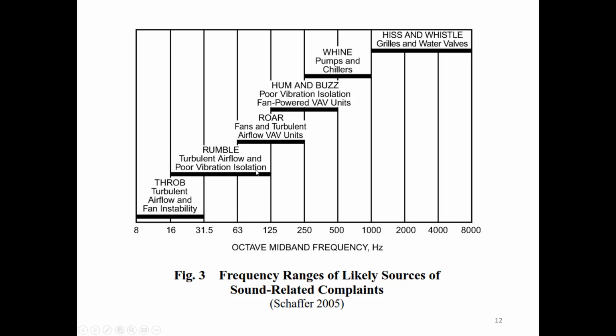Coming up in frequency, we're still dealing with poor vibration isolation and turbulent airflow. This isn't just the diffuser at the very end, but right as you're coming out of the air handling unit, if you have to make complicated turns without space to radius them, you can get a big rumbly turbulent airflow noise.